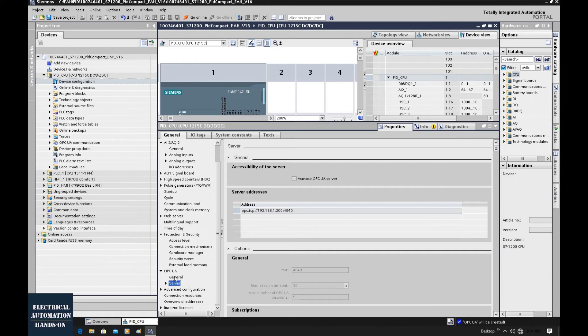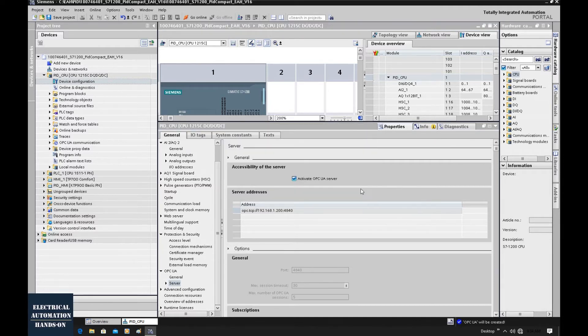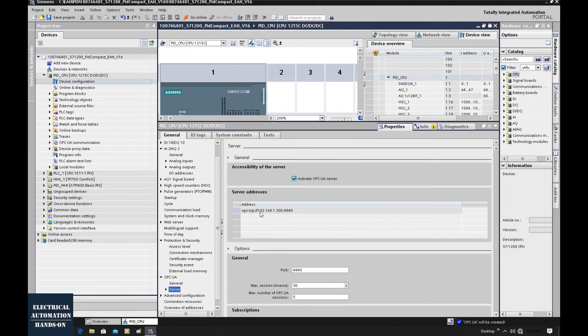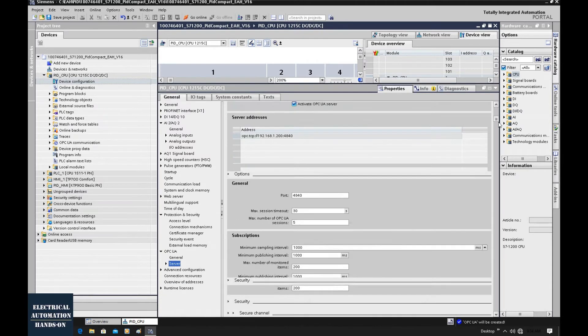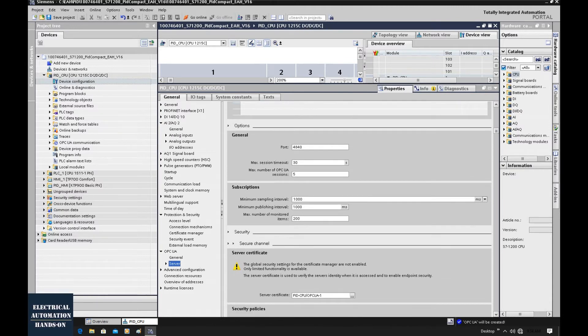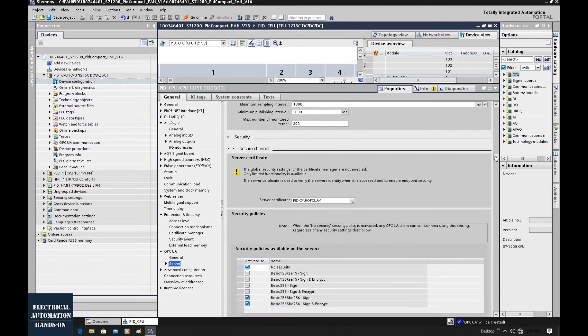To enable the OPC UA server function, let's go to the Server section and check the box to activate the OPC UA server. The current IP address of this controller is 192.168.1.200 with port 4840, so this is the full address of this OPC UA server. We can leave the default values and for the server security certificate, we will check non-security for testing purposes.